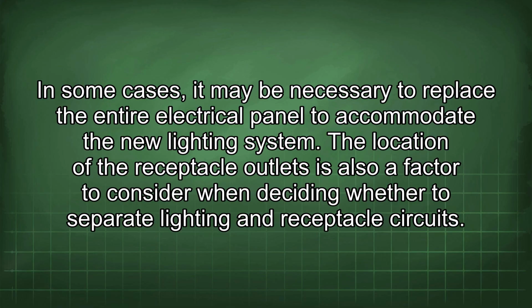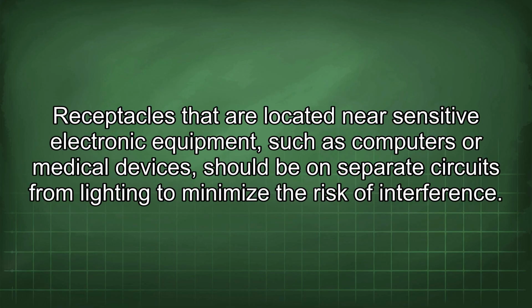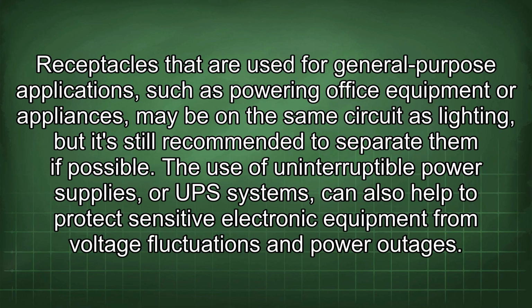The location of the receptacle outlets is also a factor to consider when deciding whether to separate lighting and receptacle circuits. Receptacles that are located near sensitive electronic equipment, such as computers or medical devices, should be on separate circuits from lighting to minimize the risk of interference. Receptacles that are used for general-purpose applications, such as powering office equipment or appliances, may be on the same circuit as lighting, but it's still recommended to separate them if possible.